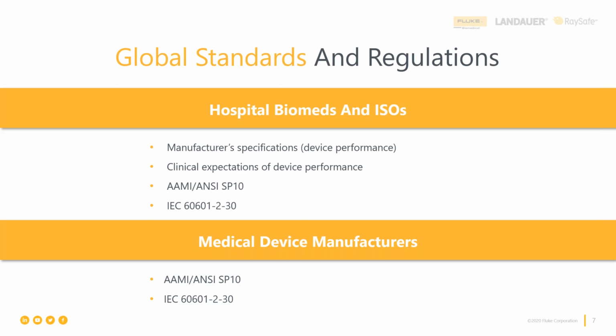You would have to do this. It's a very much longer process. You have to have a lot more clinical studies and so forth to go along with it. But just so you realize, clinical expectations of device performance play into the game, but it's really, what does the manufacturer say the specs and the device performance should be? And that's what we're going to be working with. The medical device manufacturers will test against international standards typically, because they're typically selling their product all around the world. And again, that's for design validation and sometimes also applied to final assembly testing in the factory just before that medical device is put in the box and shipped to you, the end user.